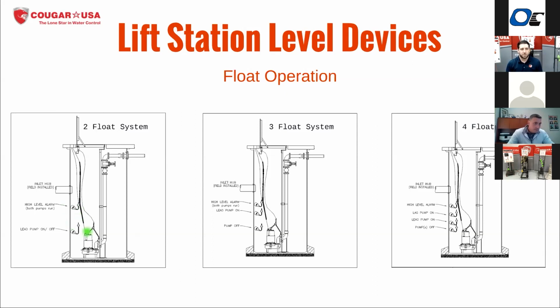Okay. So some terms that you may have heard before when you're talking about float switches: you're going to want these to be considered a wide angle float, meaning you're going to have a very long pivot point or point of actuation for that float switch, versus a narrow angle where it would actuate at 15 degrees versus 45 or the 90 for the wide angle. The reason being is that the pivot point, from where this float switch turns on to where it lays flat, is going to be the pumping range of that pump. And so we want to extend that so that we're not short cycling the pump. And you do that by adjusting this weight. The further away that float is from the weight, which is its pivot point, the longer the pump range is going to be.